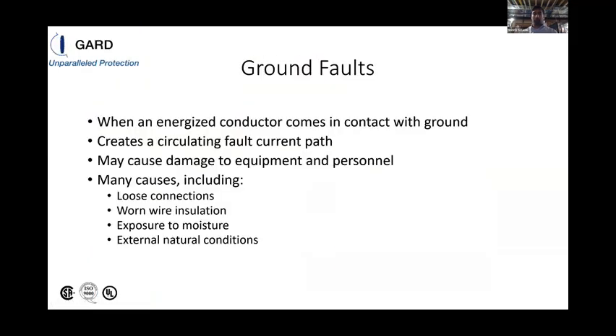Now, when it comes to ground faults, a ground fault is an unintentional path between conductors and ground that we want to avoid because it may cause damage to equipment and personnel. This is usually caused by loose connections, worn wire insulation, exposure to moisture, or even external natural conditions.